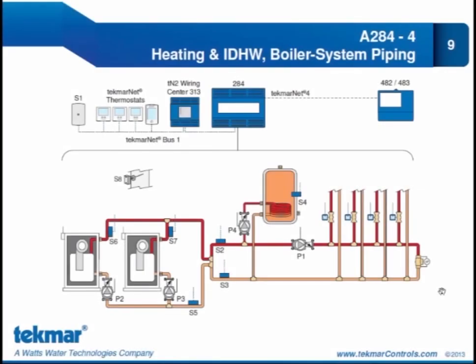This application shows two modulating condensing boilers that are being operated to provide heat for space heating and for indirect domestic hot water. This is what we refer to as boiler system piping. So the indirect domestic hot water is not near one of the boilers, it's on the boiler system, so we call that boiler system piping. We have our space heating zones. tekmarNet thermostats are all TN2 in this case. They're connected to a wiring center, which in turn is connected to the 284 to provide indoor temperature feedback.